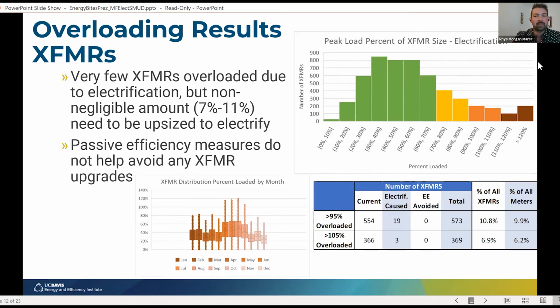Nonetheless, these are all transformers that we have to replace if we want to do electrification, so they're all worth considering. Something interesting is that the passive efficiency measures that we added do not help avoid any transformer upgrades. This is partially because of the load shape. The load shape is not necessarily helping out at the peak hours in the peak months, so that's maybe one concern. If you used a different load shape, it might change a little bit, but for the most part, the transformers that are overloaded are way overloaded already. So it's just interesting that you're not going to be able to avoid them with some energy efficiency.